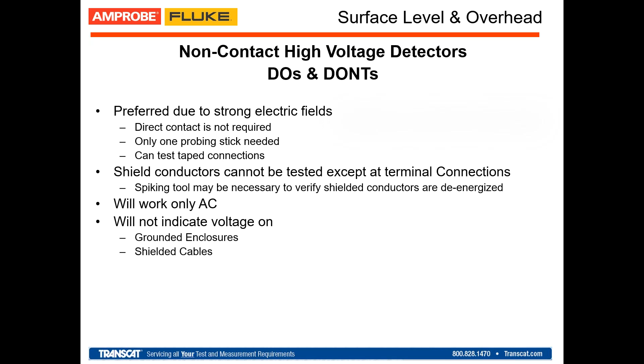Well, this is pretty intuitive too. The non-contact voltage detectors do not work with DC voltage. They only work with AC voltage. And I think I mentioned this before, they don't indicate voltage on shielded cables and grounded enclosures.